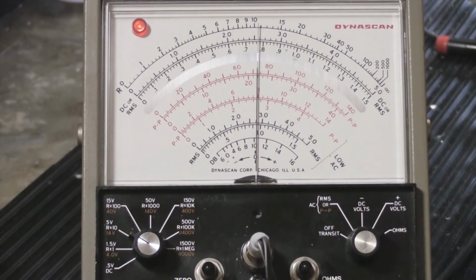Same thing is true when you null out a signal. You want to null it out to its lowest possible setting, like that. That's as low as it will go. And you've nulled it out. It's not quite 0, but it doesn't necessarily have to be. And maybe when you go back through the steps the second time, it may be a little bit lower.